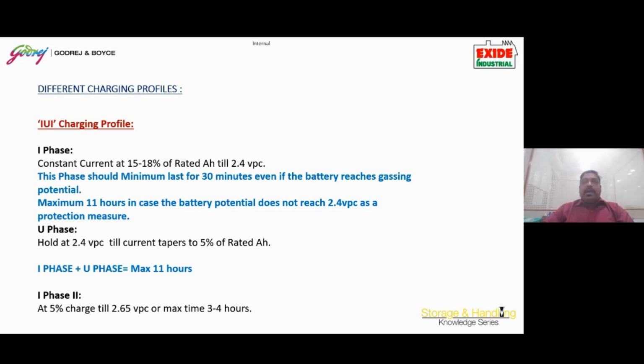As a matter of fact, lead acid batteries can be charged even up to 2.99 volt, but it will never go to 3 volt. However much you pump in, the voltage will never go beyond 2.99. So theoretically, that is the maximum that can be achieved. However, in a practical scenario, the traction batteries can be charged even up to 2.75, 2.80 volt during the commissioning. So up to 2.4 volt, it should be charged with a CC charger, which means that the current will be constant, and the voltage will be increasing steadily till 2.4 volt.